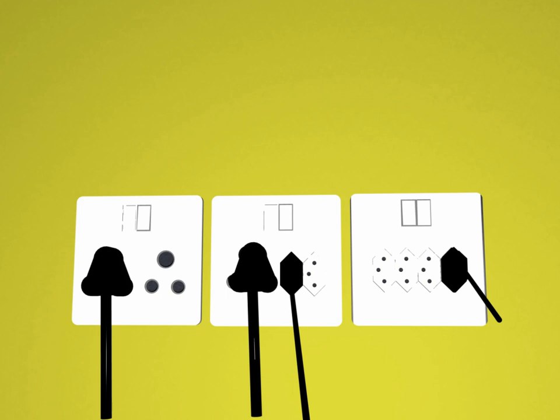The sockets are small enough that two can be installed in the space taken by a single Shuko or BS 1363 socket. The socket has either a 10mm deep recess or a 12mm high rim to exclude incompatible plugs. It ensures that the protective earth pin establishes contact before the line and neutral pins. Sockets are required to have shutters for the line and neutral apertures.